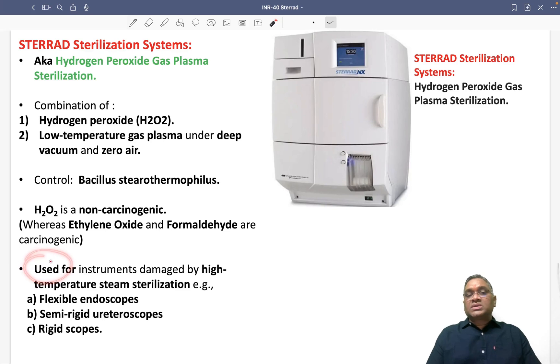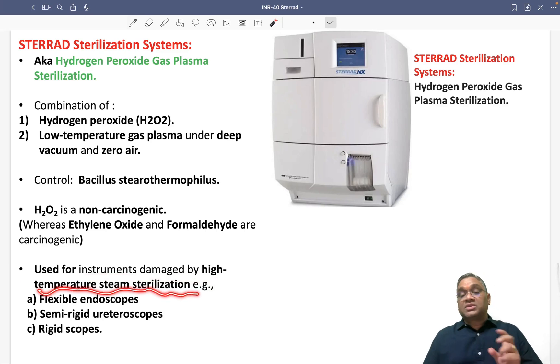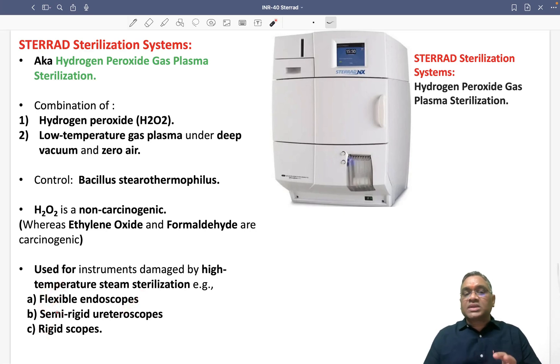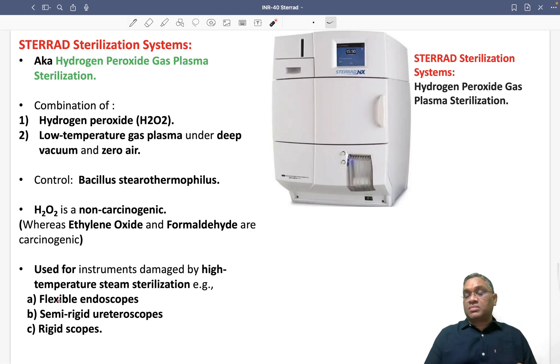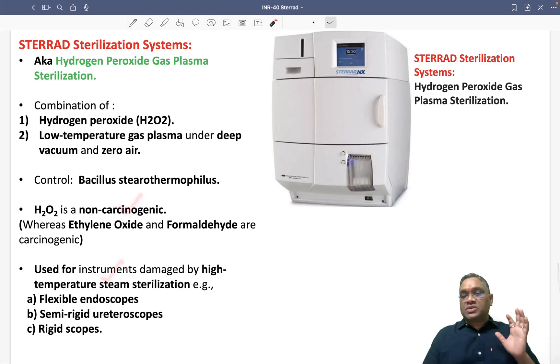So what is the use of this Sterrad Sterilization System? It is used for instruments which can be damaged by high temperature steam sterilization, like a bronchoscope, endoscope, or uretroscope. All these — flexible endoscopes, semi-rigid uretroscopes, rigid scopes — can be sterilized by the Sterrad Sterilization System. So the advantages are: it is non-carcinogenic and it can prevent steam sterilization-induced damage.